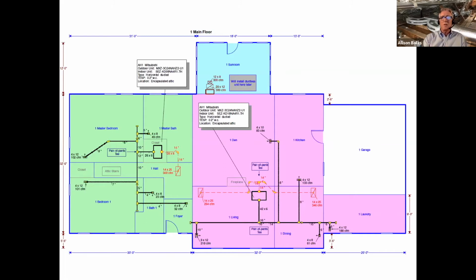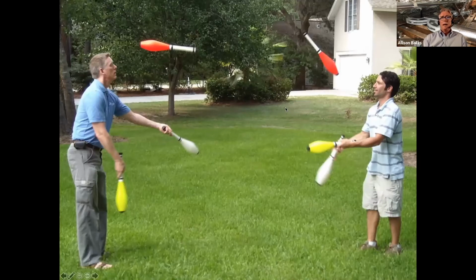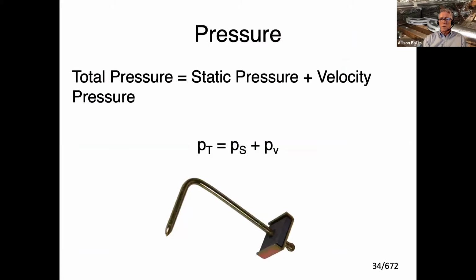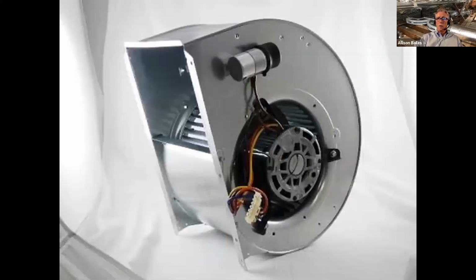And the reason it works is that I am a juggler, and duct design is really nothing but juggling. You've got some different things to juggle to make it work. The first thing is pressure. Pressure is only one factor in the equation. And when people say you can't put too much duct work on a low static air handler, they're thinking that pressure is the only thing that matters. But pressure is not the only thing that matters. Pressure comes from the blower, and HVAC guys are usually used to working with big blowers that have a lot of pressure, a lot of force, and can move the air with higher pressure.